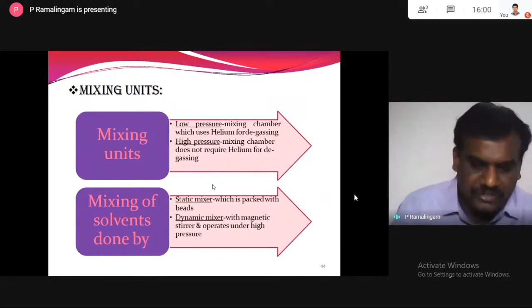And degassing of solvent: why do we need to do degassing of solvent? It's to avoid baseline noise disturbance. The reason is nothing bad. When the solvent is flushed into the column with high pressure, what happens if gas is dissolved in the solvent? Bubbling will be there inside the column. Sometimes this disturbs your baseline, and the detector performance is also disturbed. So you have a lot of error in analysis and peak distortions also.